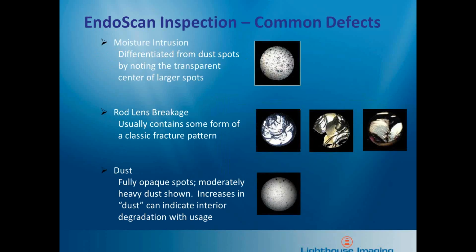This next slide shows some sample images of things you can see looking inside of an endoscope. Remember again that the EndoScan, when we look at it in a moment, is not evaluating the image quality. It's not looking at all at what the surgeon sees. It's actually looking inside at those different components of the rigid endoscope that we talked about a few minutes ago. So when we look with the EndoScan inside of an endoscope, we're looking at the ocular lens, the rod lenses, and the objective lens as we move the scope under test through the EndoScan range of motion.